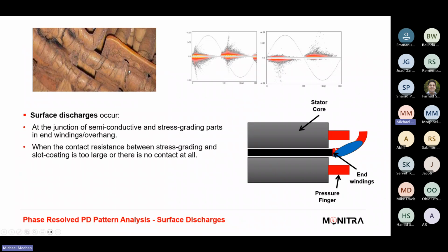That's the high voltage stresses basically trying to find a way to ground or to stressing between conductors, and really, if left in that condition, that insulation would become a real issue, and you would end up with a failure mode in time. When the contact resistance between stress grading and slot coating is too large, or there is no contact at all. So these are some of the major issues with surface discharges.